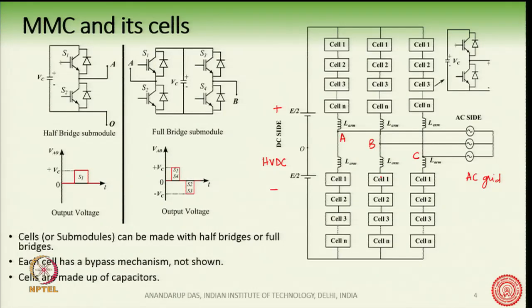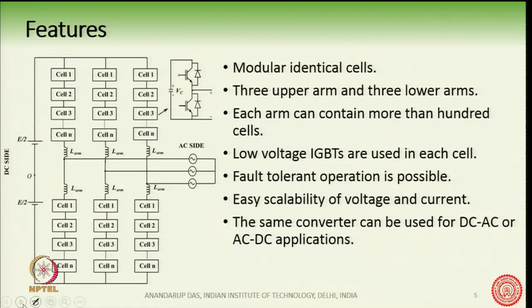The arm inductor has many functions: it can control the circulating current inside the arms and can also limit the short-circuit current in the event of a short circuit on the DC side. Each cell is a half-bridge — one of the simplest structures in power electronics — and each cell has a DC bus made up of a capacitor, so there is no need for any isolation.